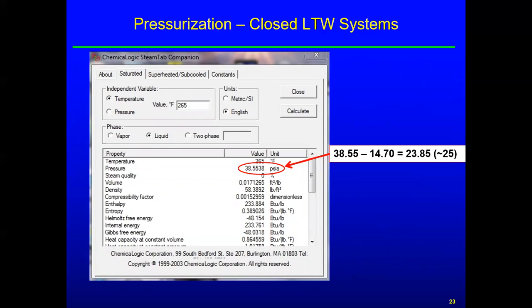So using the Steam Tab Companion: design maximum water temperature is 250, add 15 to get 265, click liquid, click English units, calculate — it comes back 38.55 psia. Remember you've got to be clear between absolute and gauge. Take off 14.7 or 15 for gauge, and you get pretty close to 24 — and that's where the 25 comes from on the slide. It's just rounded up to 25. That's an example of actually doing that calculation.